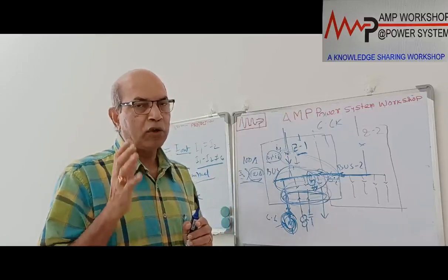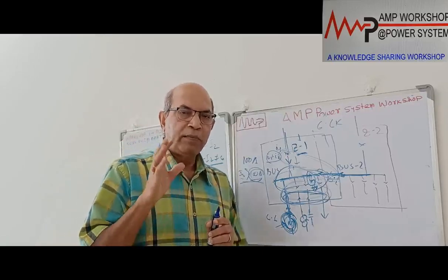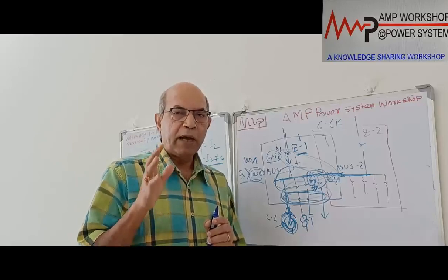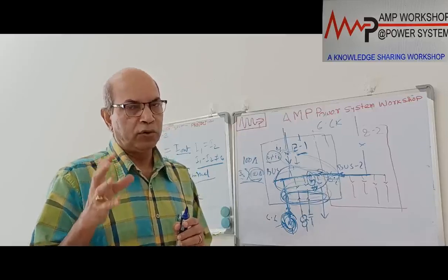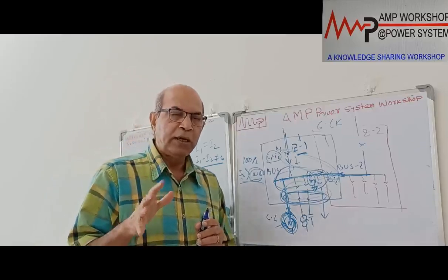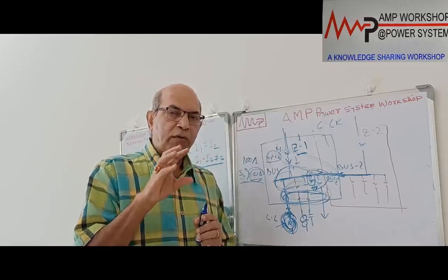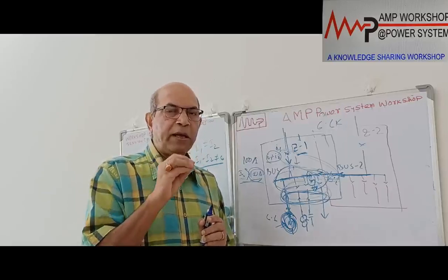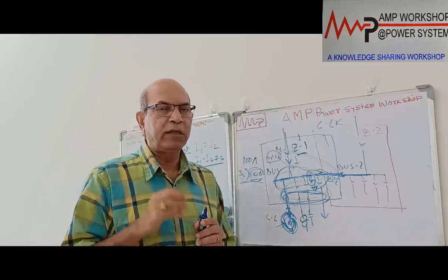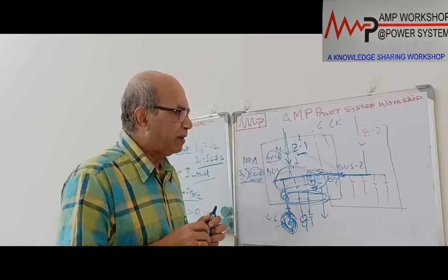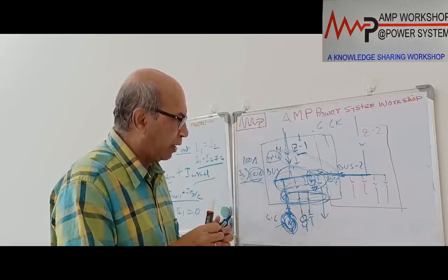The maximum possible outgoing current is calculated based on the normal running current plus the maximum starting current of the largest load. This sum will be the total outgoing current. When the incoming current is more than that maximum outgoing current, the relay will understand there is a fault on the bus bar. That is the basic principle of the partial differential scheme.